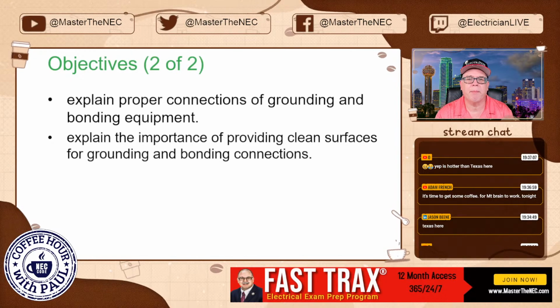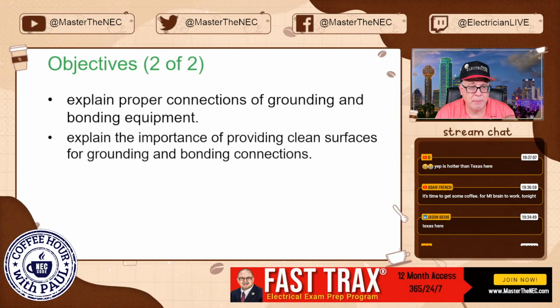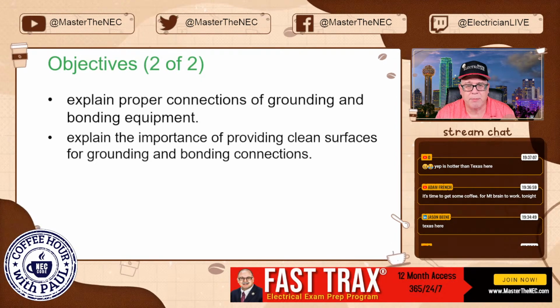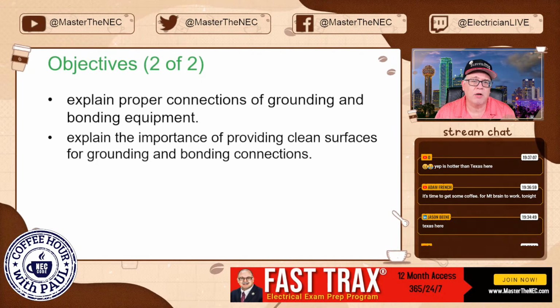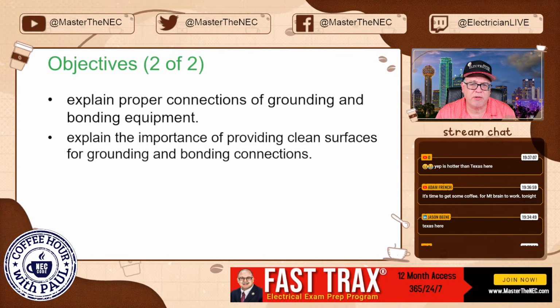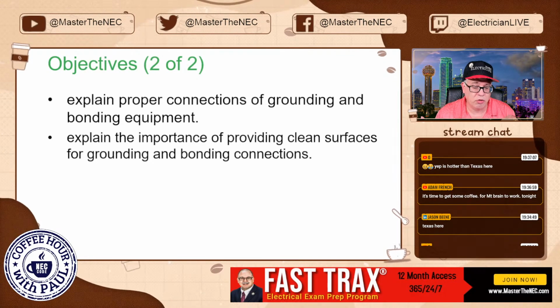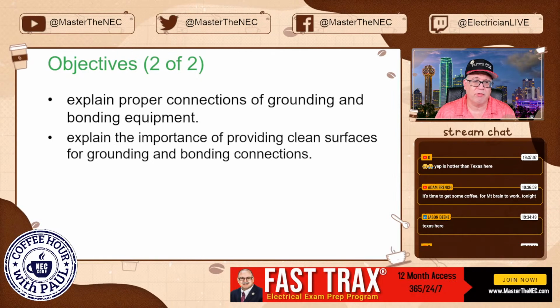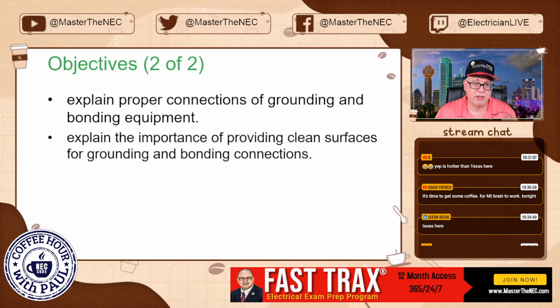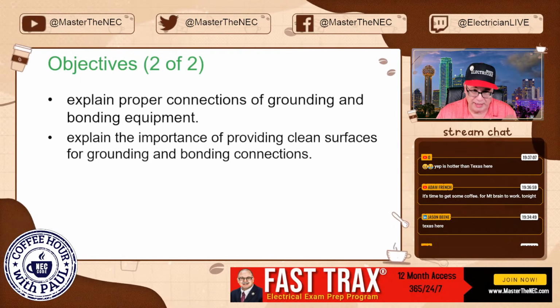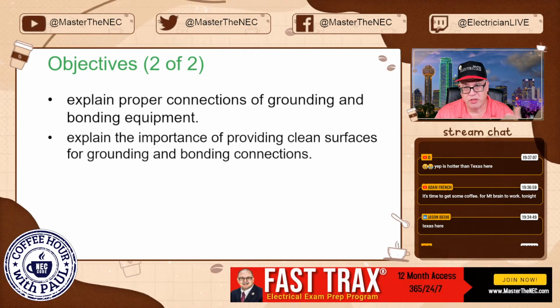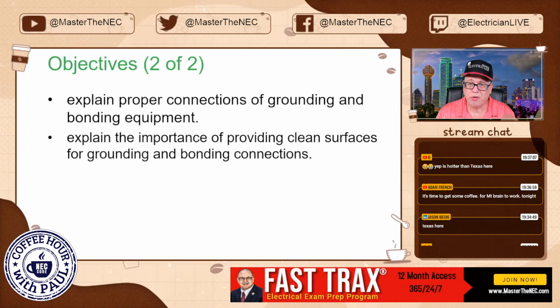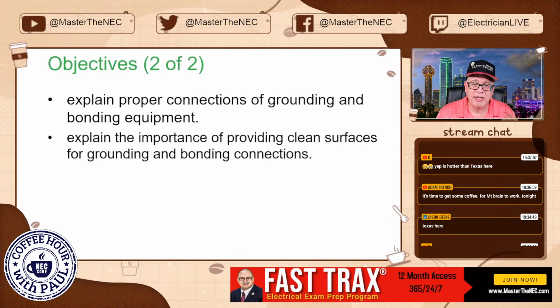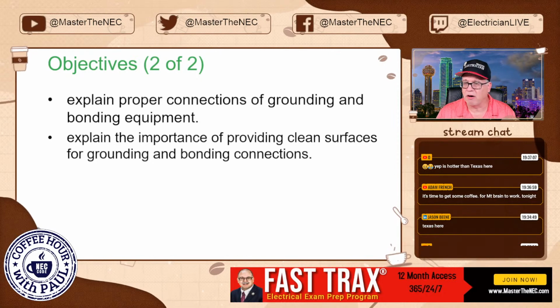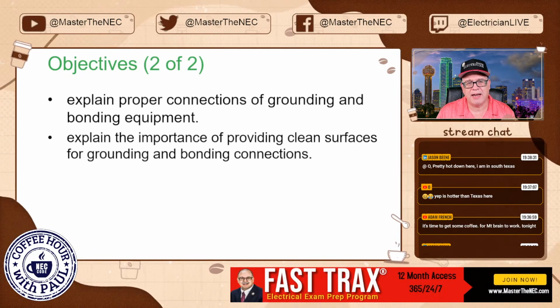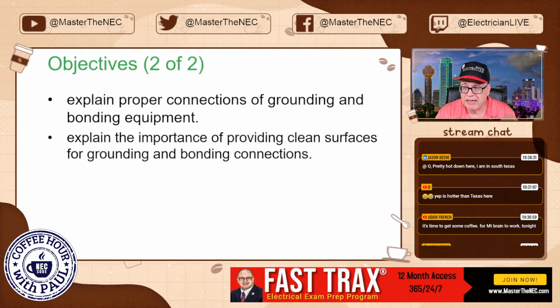We're going to explain proper connections of grounding and bonding equipment. Again, we're going to be talking about 250.8 and proper termination and whatnot. And we'll explain the importance of providing clean surfaces for grounding and bonding connections. Again, your reliability of clearing an overcurrent protective device is only as good as your low-impedance effective ground-fault current path. Remember, we talked about that back in part 1 and part 2. Well, if your connections are poor, you're not wrench tight where you need to be, and your surfaces are not clean, not making good contact, then the chances are you're not going to get the desired effect.